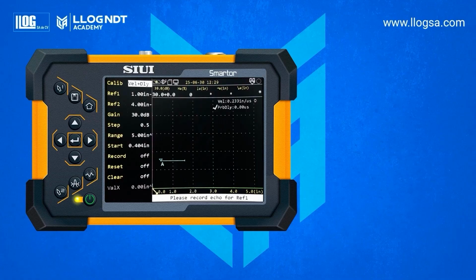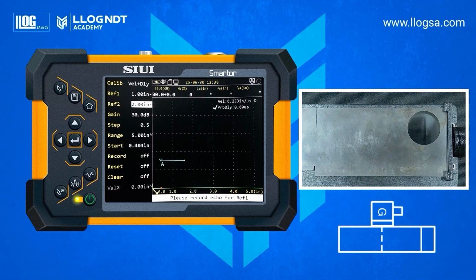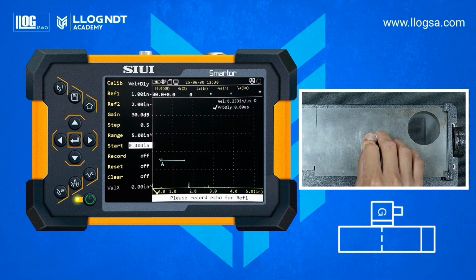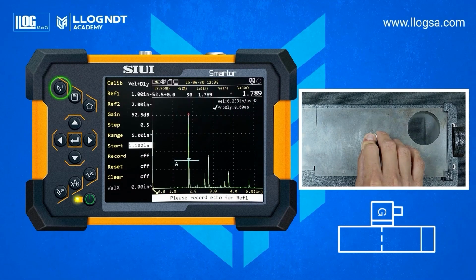Now go to the Auto Calibration submenu, and we will perform the calibration using multiple echoes. The first reference is 1 inch, and the second reference is 2 inches. Place the transducer in position G on the calibration block. The gate must be placed over the first echo. Press the F1 key so the amplitude reaches 80%. Then press Enter on the Save function to store the first reference. Now move the gate to the second echo, corresponding to 2 inches, and press the Save key again.